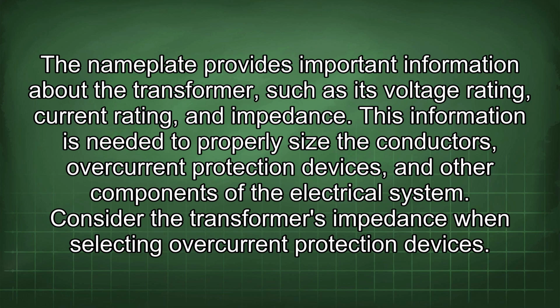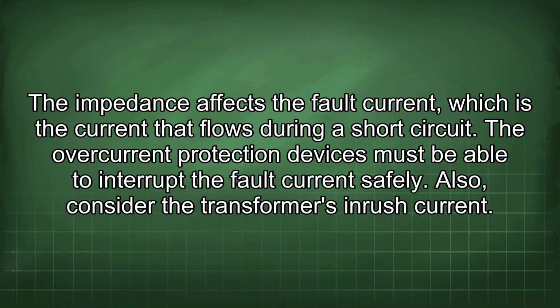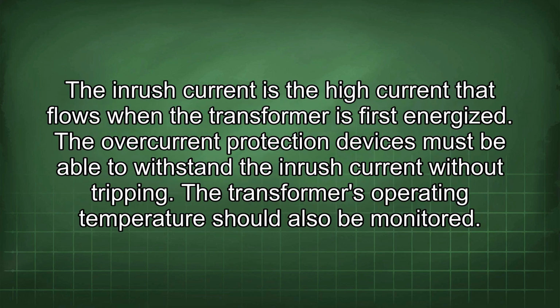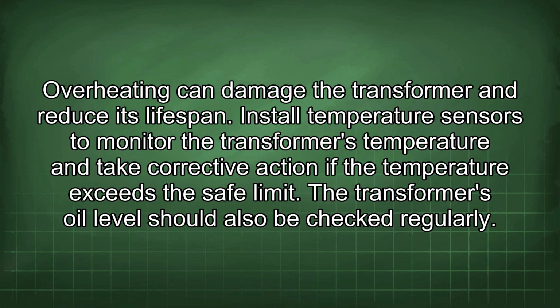Consider the transformer's impedance when selecting overcurrent protection devices. The impedance affects the fault current, which is the current that flows during a short circuit. The overcurrent protection devices must be able to interrupt the fault current safely. Also, consider the transformer's inrush current. The inrush current is the high current that flows when the transformer is first energized. The overcurrent protection devices must be able to withstand the inrush current without tripping. The transformer's operating temperature should also be monitored. Overheating can damage the transformer and reduce its lifespan. Install temperature sensors to monitor the transformer's temperature and take corrective action if the temperature exceeds the safe limit.